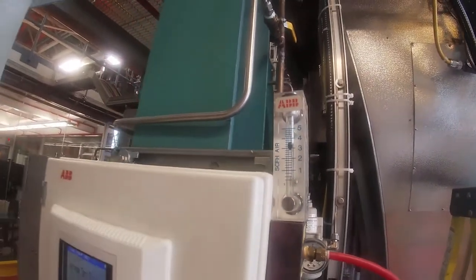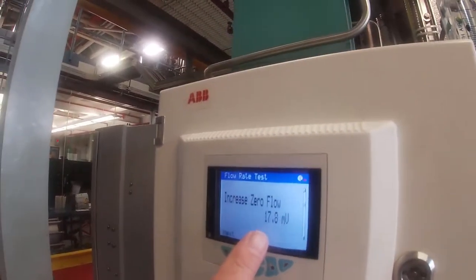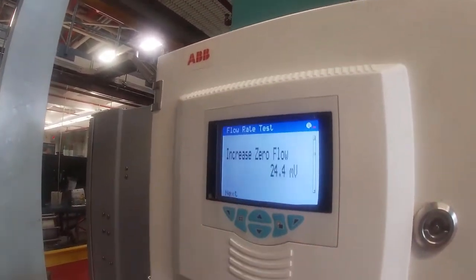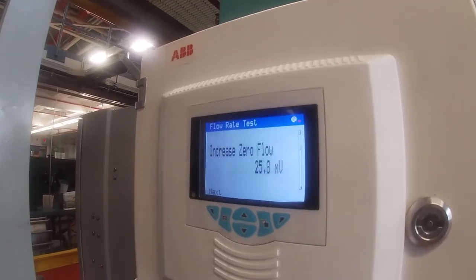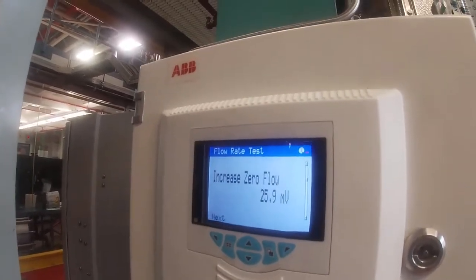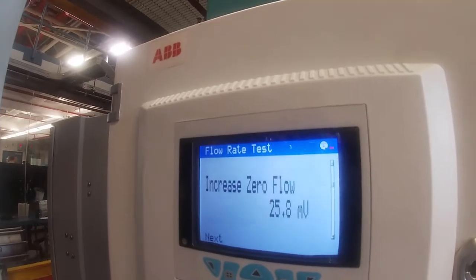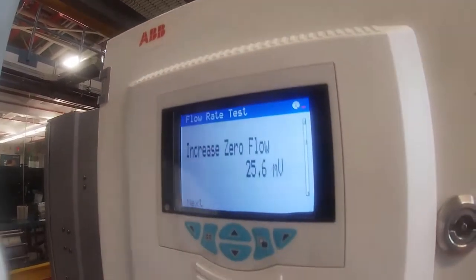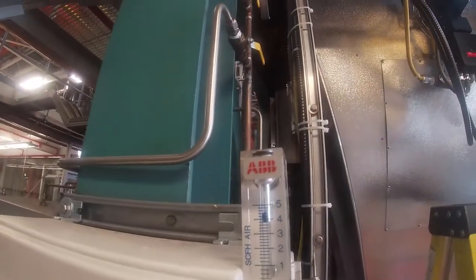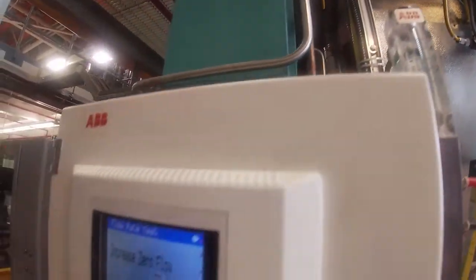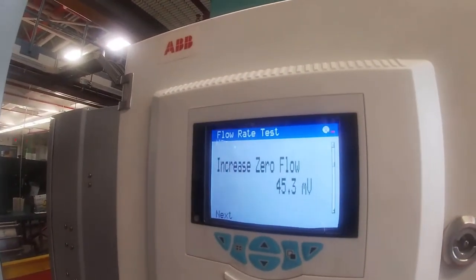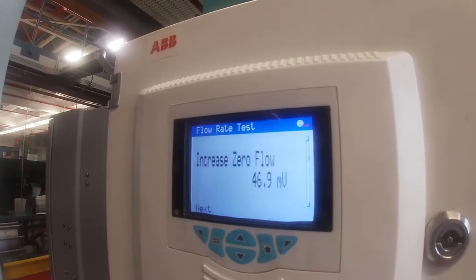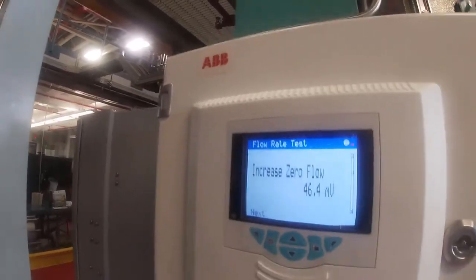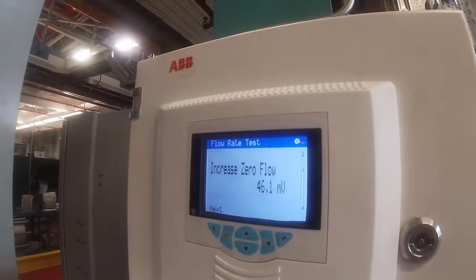Not much happening there. I've just gone up to 3, and you can see the number starting to move now. We've gone to positive 24, still climbing, 25, and it looks like it's kind of leveled off. I'll give it a little more gas. So I'm up at 4 standard cubic feet now. Now it's gone to 27, 45. Numbers coming up pretty good. 46.